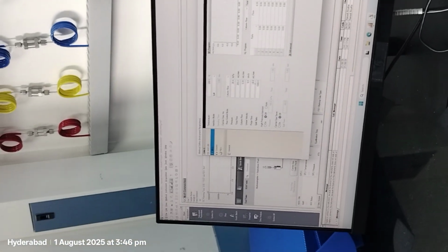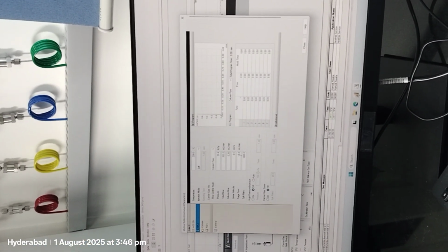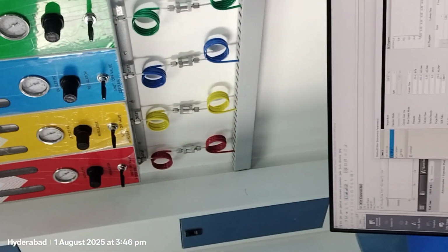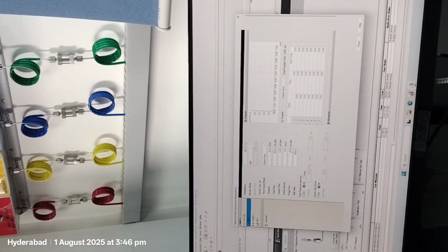Up to how much can we give? 3 ml is enough. Default. In HS also you can give, no problem. We can give 10? No, we have to give only 3. Why? Because, as we told yesterday, that is for sweeping the rubber septa. Yesterday you saw the blue color. 3 ml will go for rubber septa cleaning. By default you have to give 3 ml only. You can give 3 to 5, up to 5, but 3 is best for you.